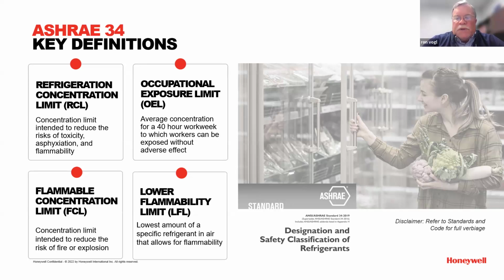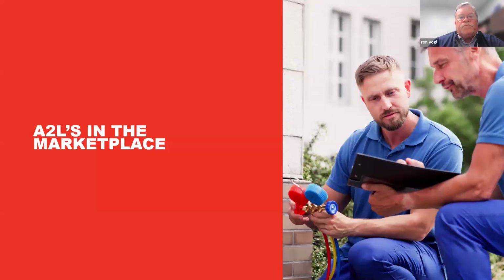Don't assume that if you're using a 404 replacement that's an A2L, you can retrofit to another one, because someone may have gone to the max charge, and by switching you could go over the allowed charge size. So more to come on that. The manufacturers are gearing up to do a good job on what's going to be required.